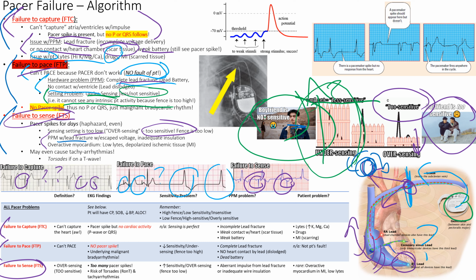Okay, so why would this happen? Why would you have failure to sense? It could be because voltage maybe is just escaping down this fractured lead. That could be a reason, but really it's a problem with the settings on the pacemaker. Okay, so I have a sensor problem. I'm not sensing things adequately. I could have a hyperactive myocardium that's responding to everything, but more commonly than not, it's because of a sensitivity issue, right? So we look at sensitivity.